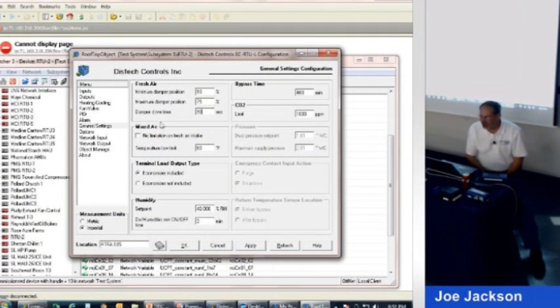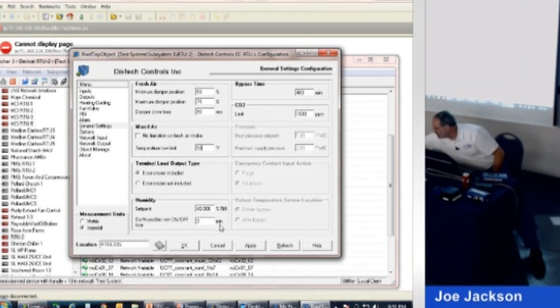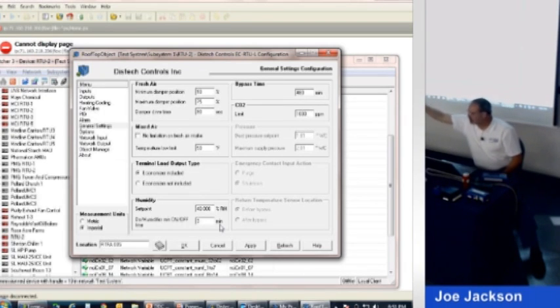If you did have a mixed air temperature sensor, and you don't want the mixed air to drop below 60 degrees or whatever, typically we would probably set this at 50 degrees because the mixed air takes the average, and our freezestat is going to trip off if any 1-inch section of it drops below 38 degrees. So as long as we keep the mixed air average at 50, we're probably not in much danger of tripping the freezestat.